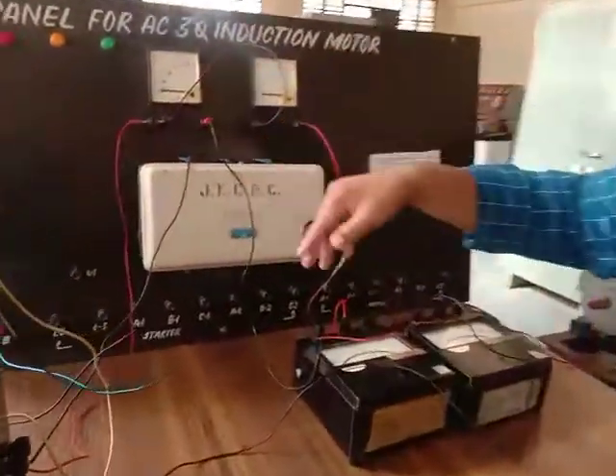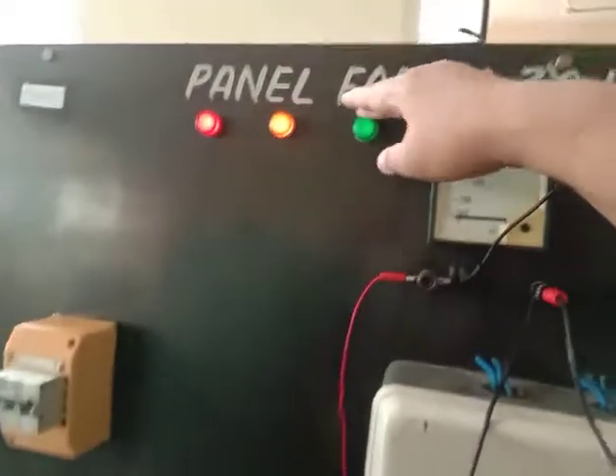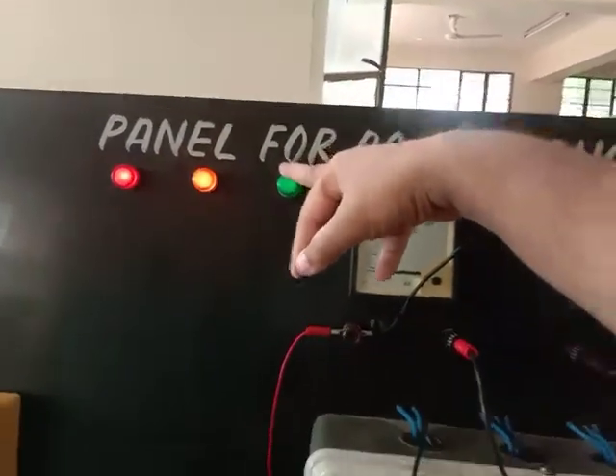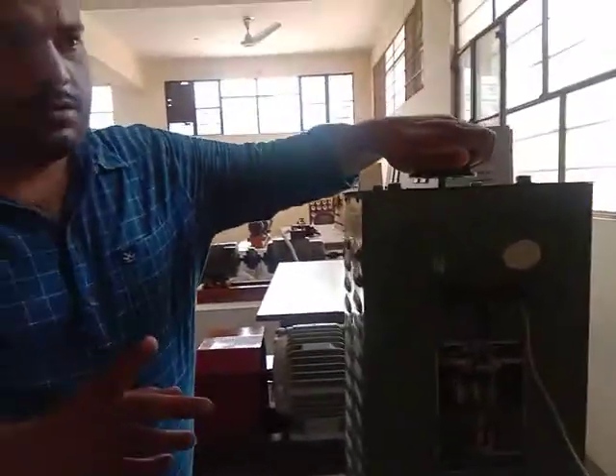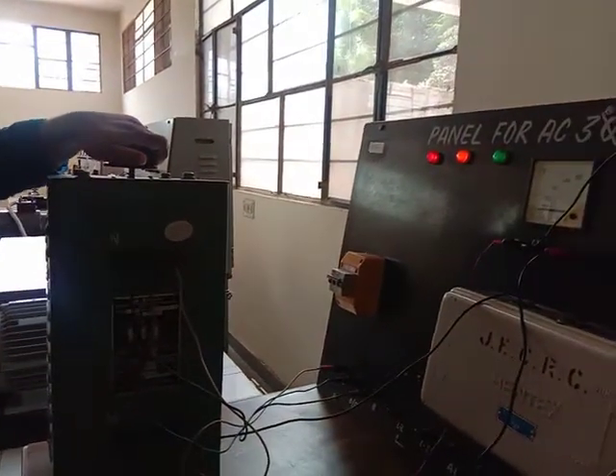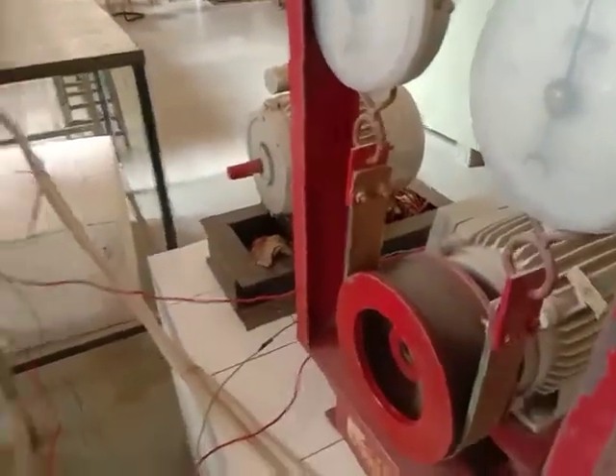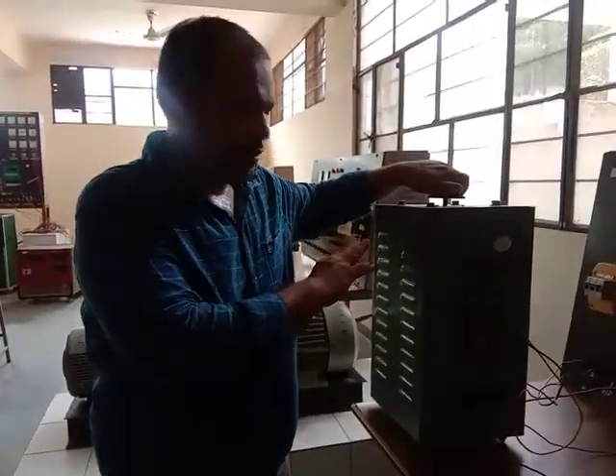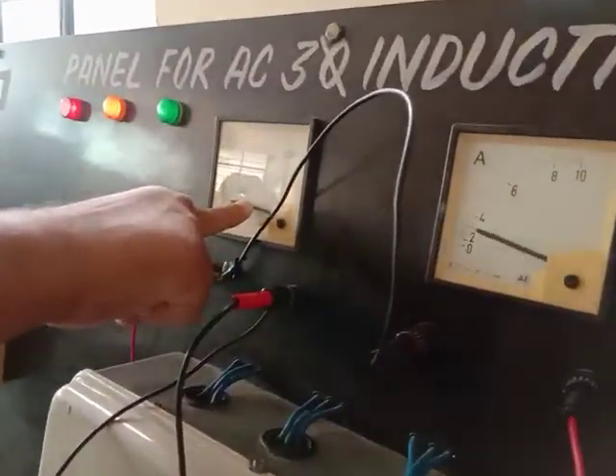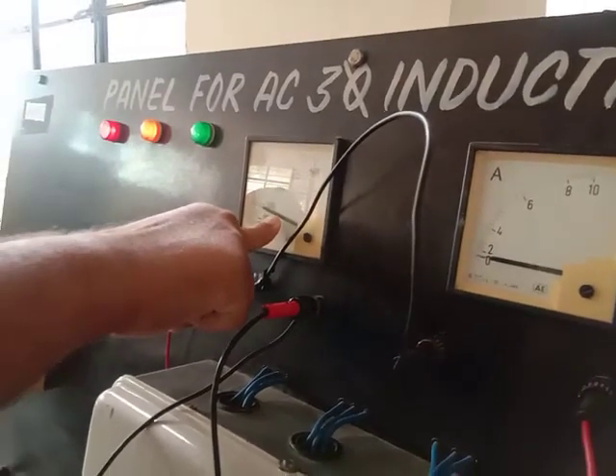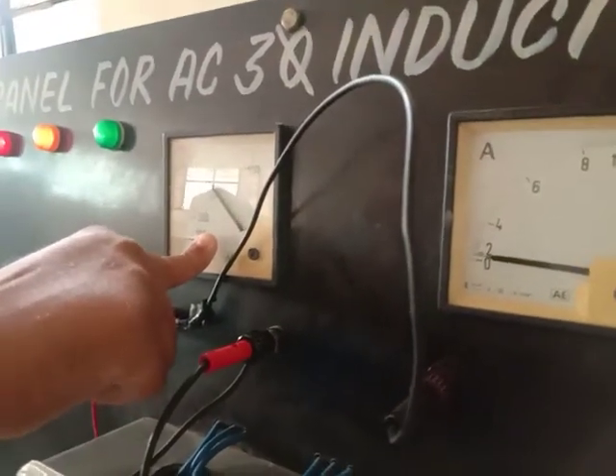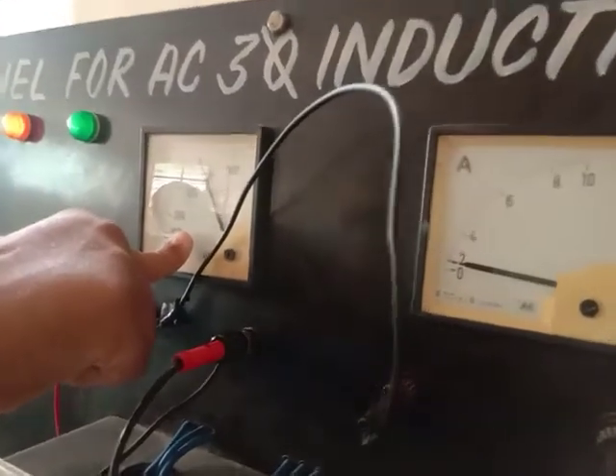So now I am switching on the supply. Here you can see all three lights are glowing. It means the supply is connected. Now this is the auto transformer by which I will increase the supply voltage, and when I increase the supply voltage, there will be a corresponding increase in the voltmeter reading, and when the supply is connected, the rotor will run from the standstill condition. So now I am increasing the voltage. You can see the voltage is increasing, and I'll increase this voltage till 400 volt, which is the rated voltage. Now it is 400 volt.